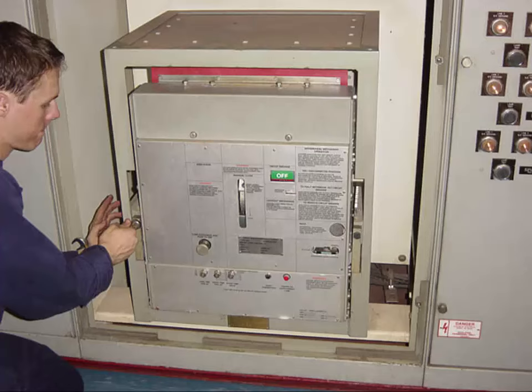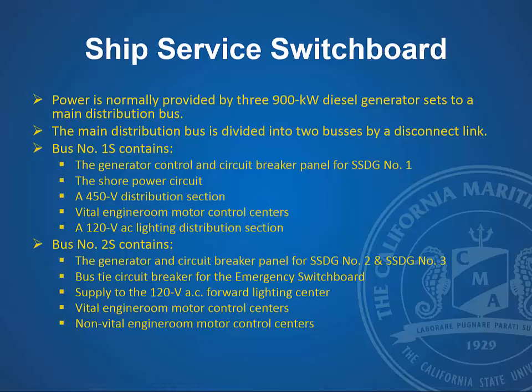It's usually 110 volt single phase that charges up a set of springs that opens the contacts very quickly and closes them very quickly to reduce the amount of arcing damage to the breaker. So we are talking a little bit about the Golden Bear because that is a ship that you're used to, that I know that you've had some experience with. So let's talk a little bit about her main switchboard.